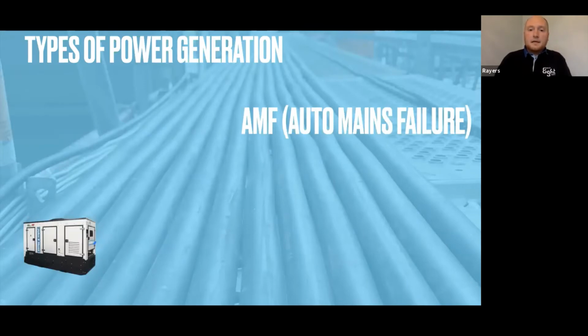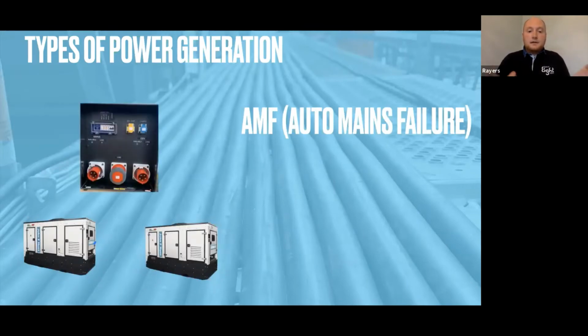Another option is automatic mains failure, where we take two generators to the distribution board, and they common up at one place. We then run a communications cable to one of the machines, which acts as standby - it doesn't run, it just sits there - while the other machine runs. In the event of a power failure, the board opens the circuit breaker to disconnect it, then sends a signal to the standby generator to start. Once it reaches 1500 RPM, the speed it needs to spin at, it re-engages the breaker and the supply continues.